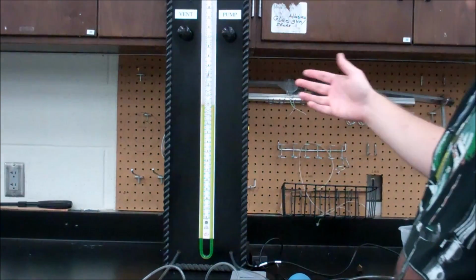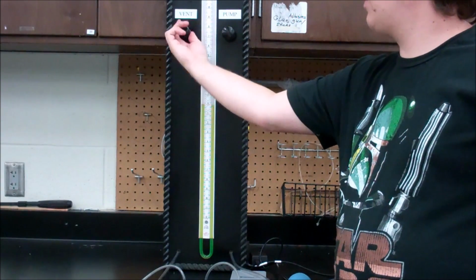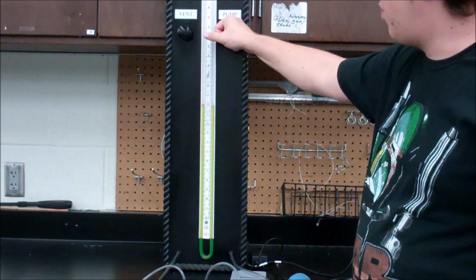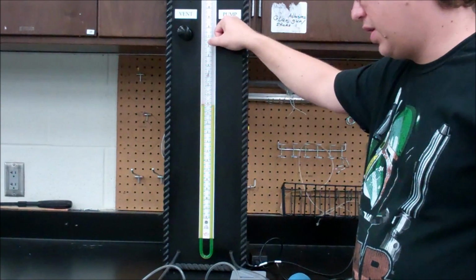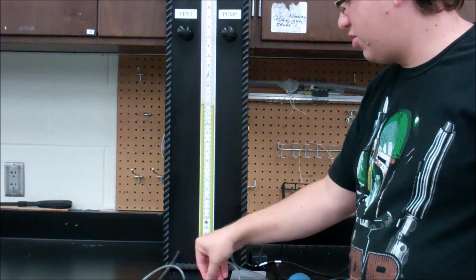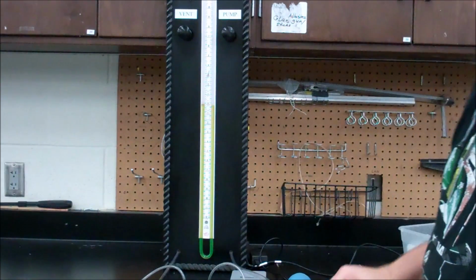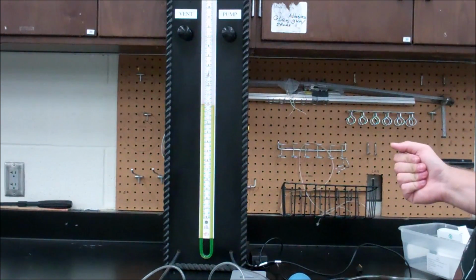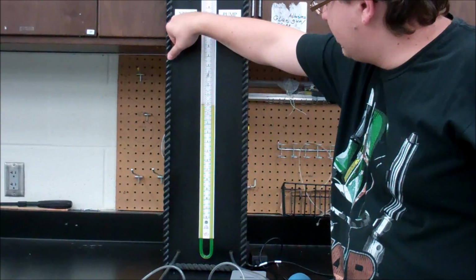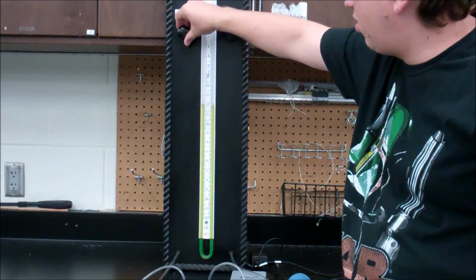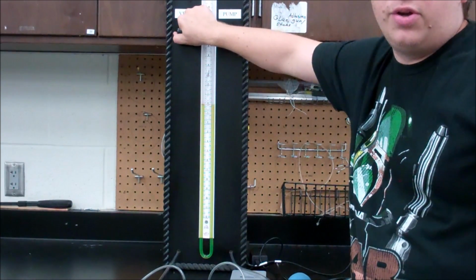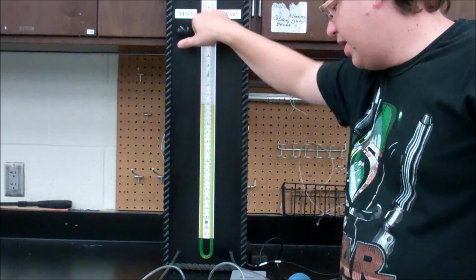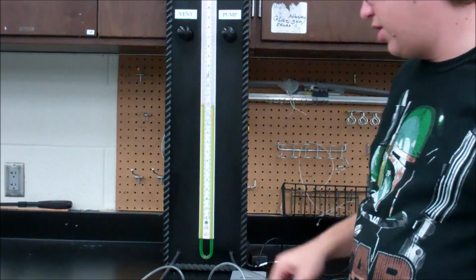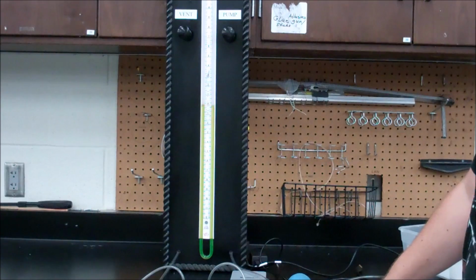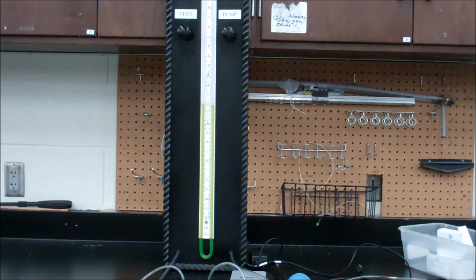Now, if the manometer doesn't work, make sure that your vent valve is turned to the right all the way and that you have your pump valve open a little bit so you can apply a pressure. Also make sure that there are no leaks by your pressure transducer or the T-junction that are causing the manometer not to function. And if you notice your manometer is not reading 0 or not reading the proper change, then make sure you vent your manometer all the way. Now if the pressure transducer light doesn't light up, check your connections and make sure they're all connected. So this is how you set up the pressure transducer and the manometer in this section of the lab.